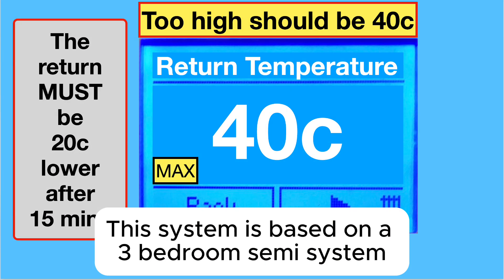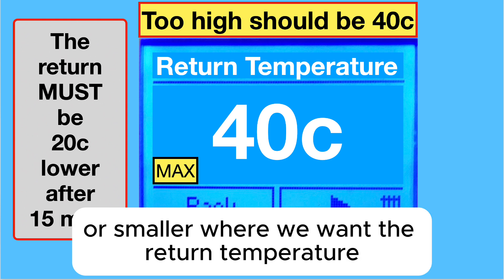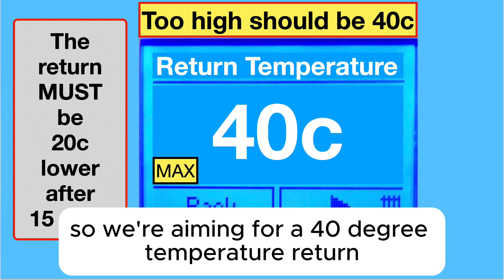This system is based on a three-bedroom semi-system or smaller, where we want the return temperature to be 20 degrees lower than the flow. So we're aiming for a 40 degree temperature return.